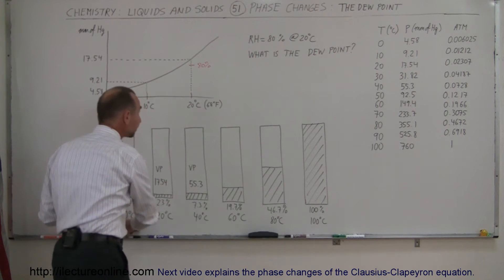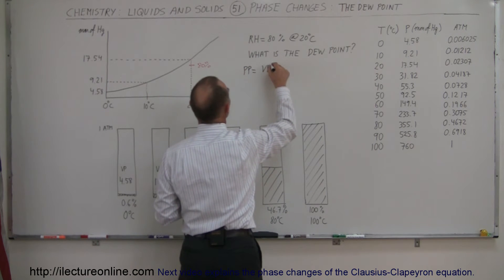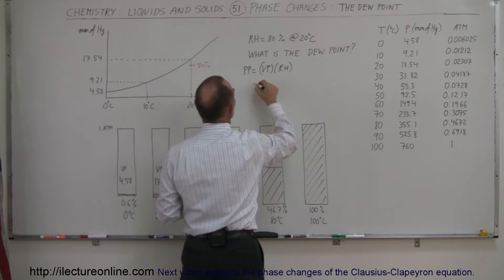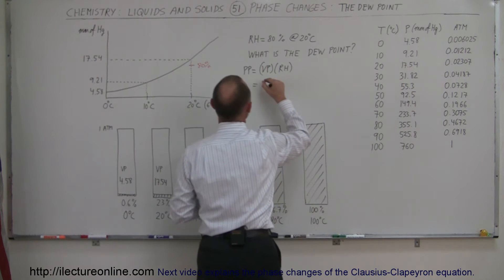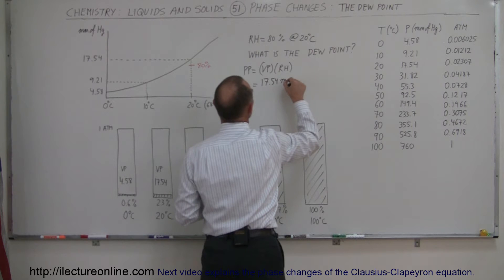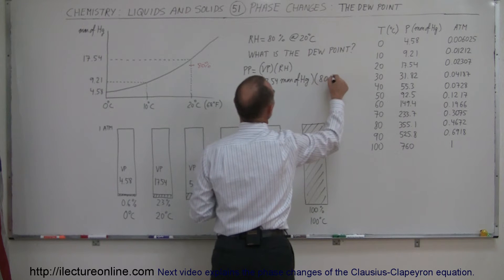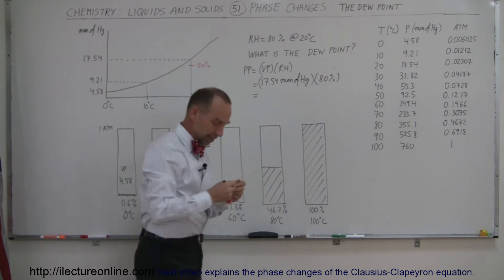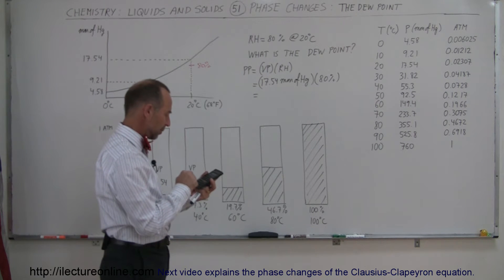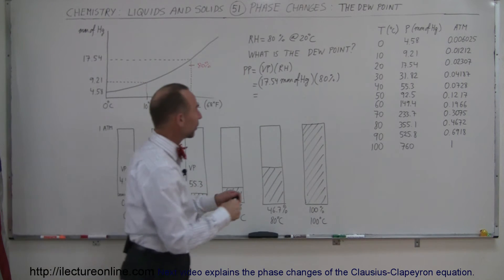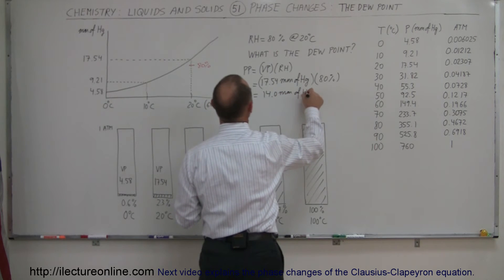So let's try to figure that out. We can say that the partial pressure is equal to the vapor pressure times the relative humidity. So the maximum moisture the air can hold at 20 degrees centigrade is the vapor pressure, which is 17.54 millimeters of mercury. And if we multiply that times the relative humidity, which we presume to be 80%, we get 17.54 times 0.8 equals 14.0 millimeters of mercury.